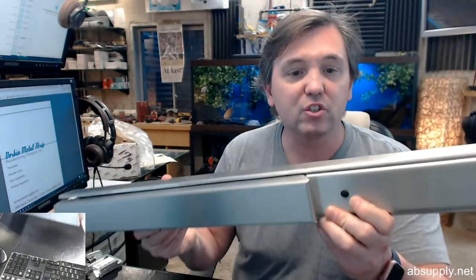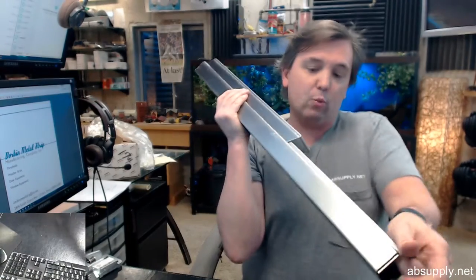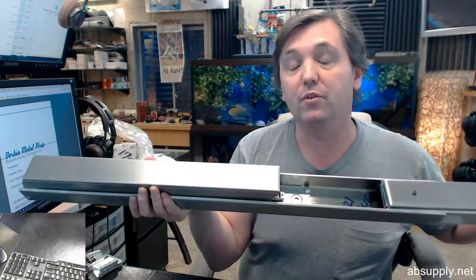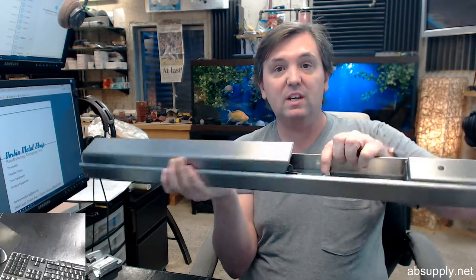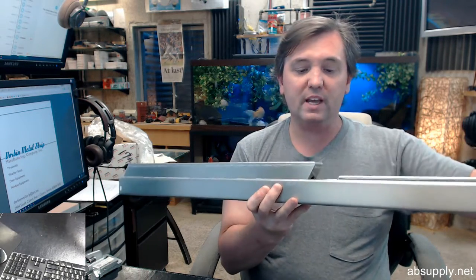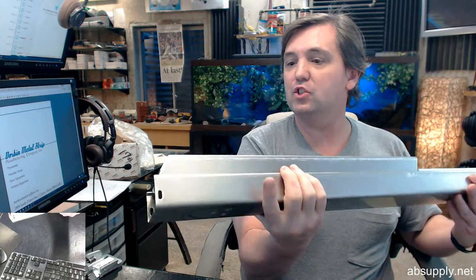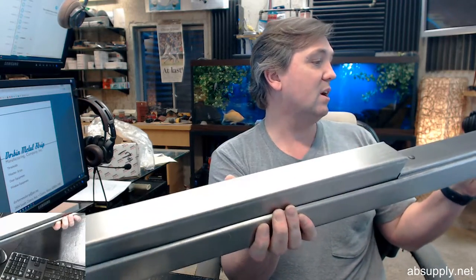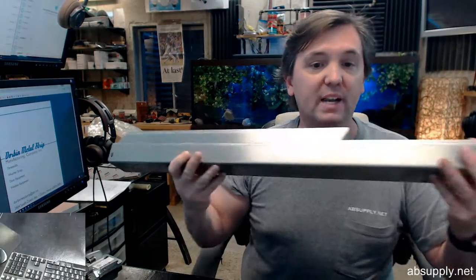This being an F device, you're not going to have any cylinder dogging. That's just going to be a cap that's there, and there will be no internal structure for hex key dogging either. I said cylinder dogging earlier. I meant hex key dogging. You can't have any sort of dogging on a fire-rated device. This device is shown in stainless steel. Its scratched surface that you see, of course, is just the peel-away protective film that's all over the body itself of the touchpad assembly.